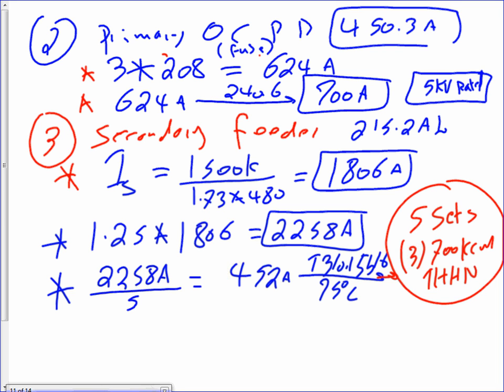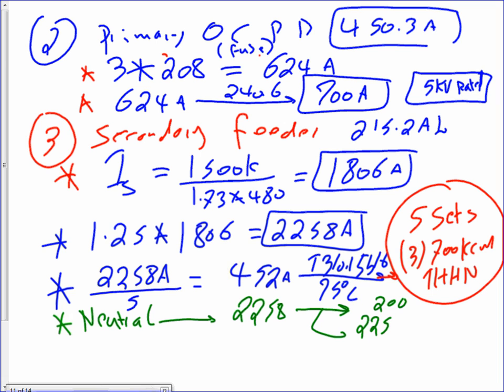Now the neutral. For the neutral, guys, when I use the same calculation, I get the same amps, because I do have a neutral here. So I will take 2258. Let's take the first 200, leave them alone. Take 2258 minus 200 and multiply by 0.7. Add everything up, and you're going to end up with 1641 amps.